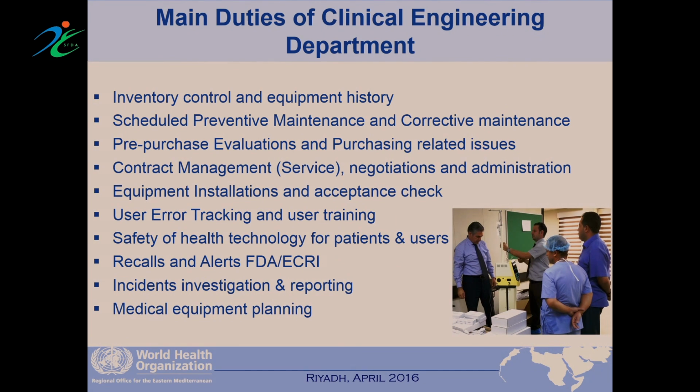And then you have to link whatever incidents are happening, you have to report on those incidents, and you have to ensure that somewhere within the hospital or the country there are regulatory people who can then put in place regulation that will address those kinds of incidents, recalls or adverse reporting. And then you need to ensure that you are planning for your equipment ahead of time, to be proactive in this kind of management, and not to wait until the end and then look for actions, and always be blamed that you are taking too long to procure equipment and to ensure that you are doing the right thing on time.